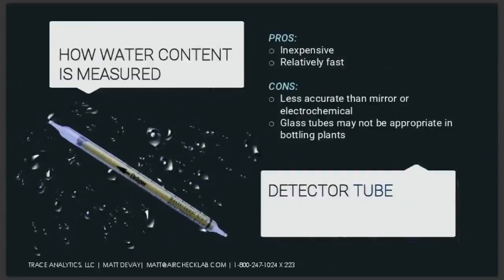One of the most common ways to detect water vapor in gas streams is detector tubes. These work with a chemical stain. It's a chemical reagent that progressively changes color as water vapor in the air interacts with the media. They're cheap, they're fast, super easy, but they do have a few drawbacks. They're definitely significantly less accurate than the previous two methods, though they tend to be fairly suitable for most cases. The reading of the tube has a subjective element to it, which feeds into that inaccuracy. They use a non-linear scale, and so when you're reading a mark between 80 and 100 on the tube, you don't really know if that's 90 or 88 or 92. They can be a little challenging to get an accurate reading off of.